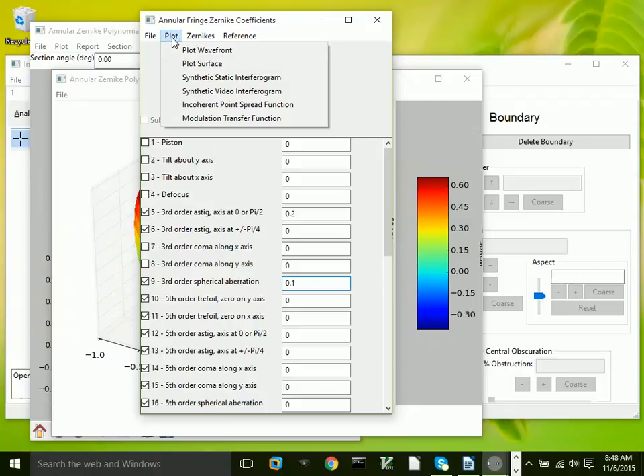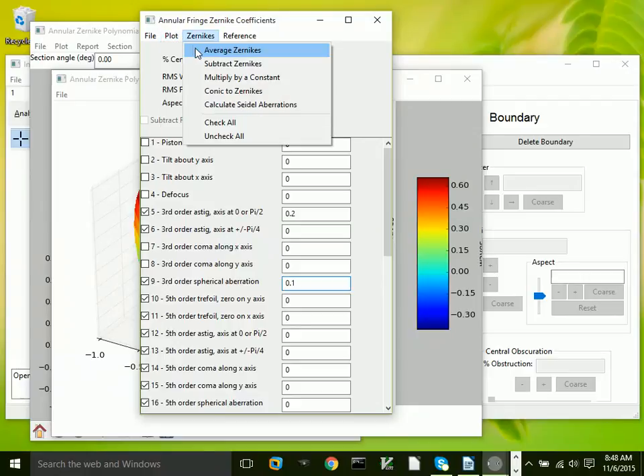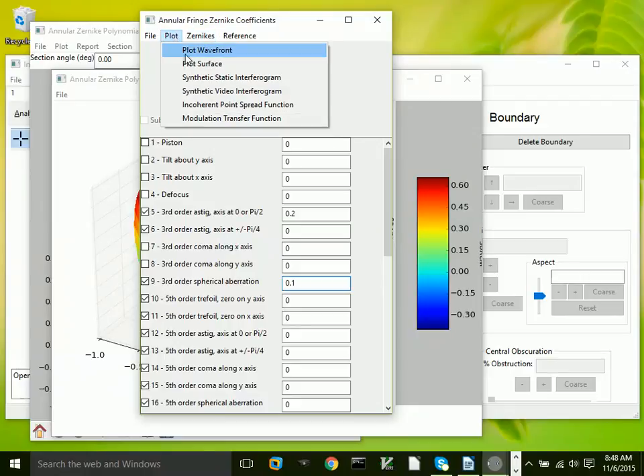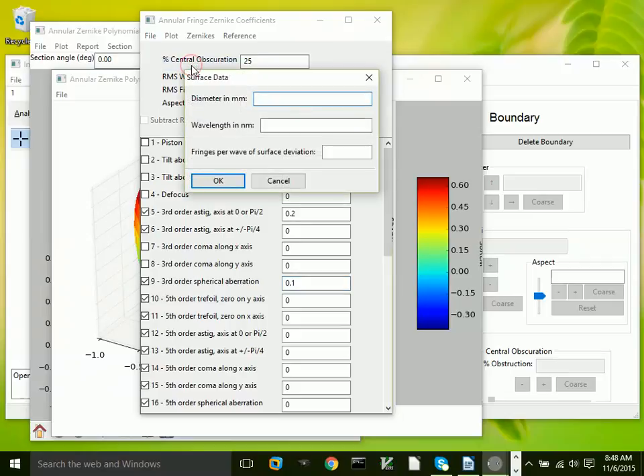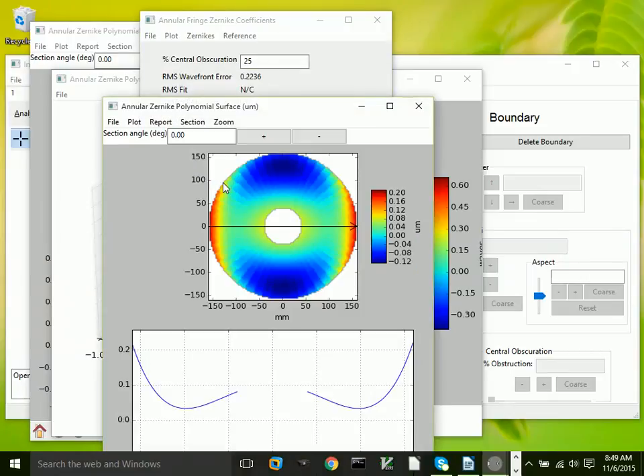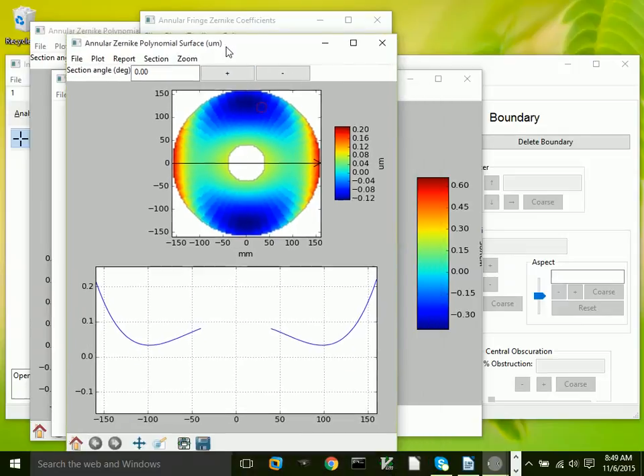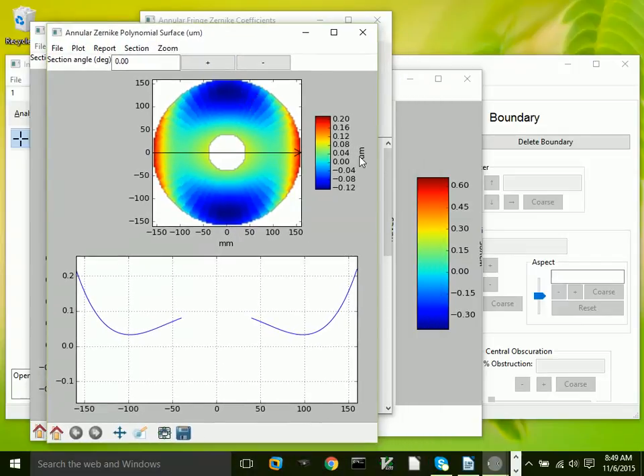In addition, we have the ability to plot a wavefront and a surface. We can plot a surface here. You have to tell the program what the parameters of the surface are. In this case, this is a reflection interferogram, so it's two waves of wavefront for every wave of surface. Now we have a plot of the surface, and it's in microns instead of waves.